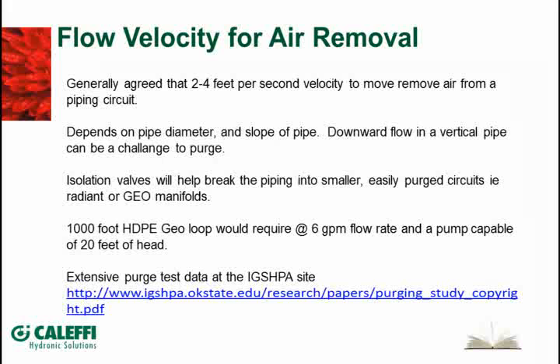Think of a 2-inch pipe that's coming down from an upper level, and you're trying to push the air ahead of the fluid as it comes down there. You've got to have enough flow, so to speak, to plug the hole in the pipe so that you're able to push the air back down with it. What can help you with systems like that is being able to isolate it and break it down into small pieces instead of trying to purge the whole job at once.